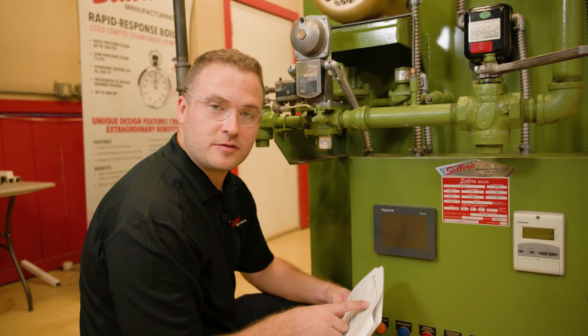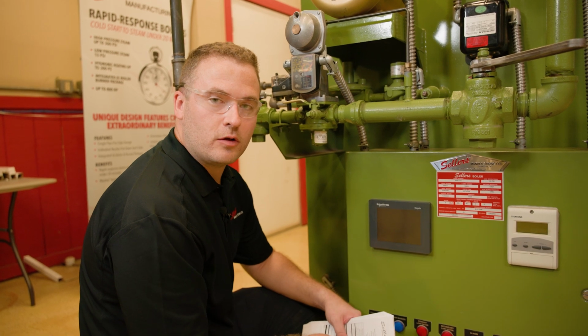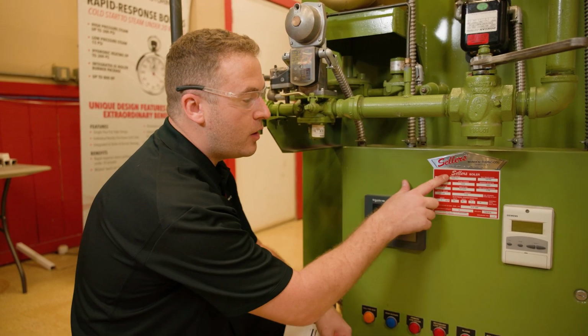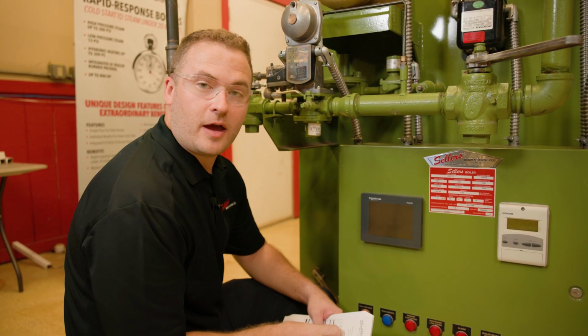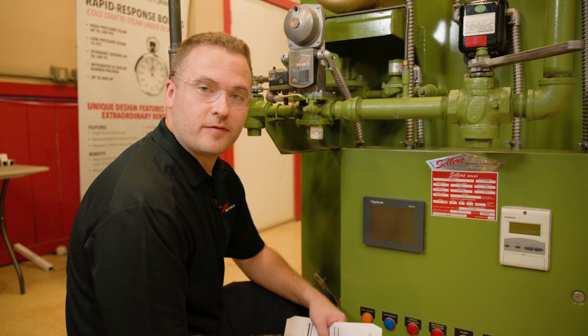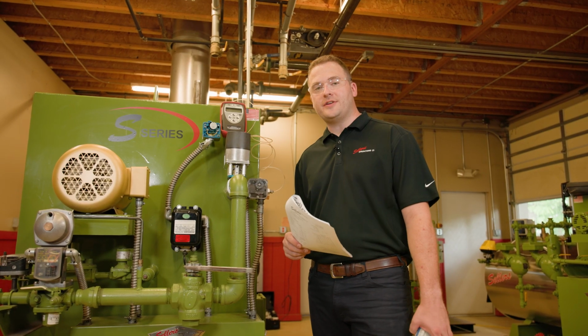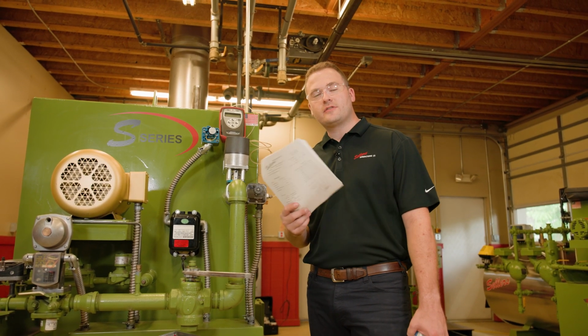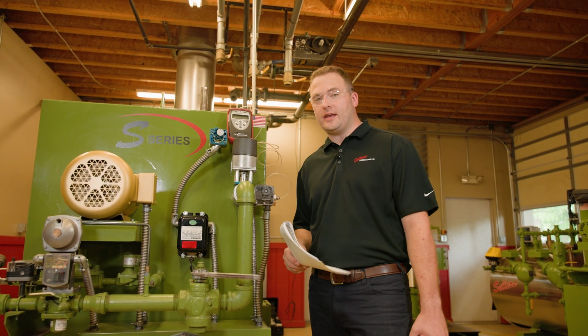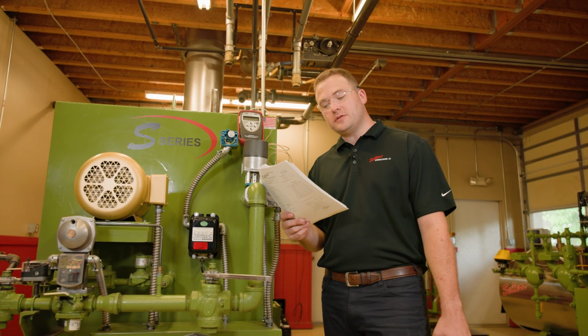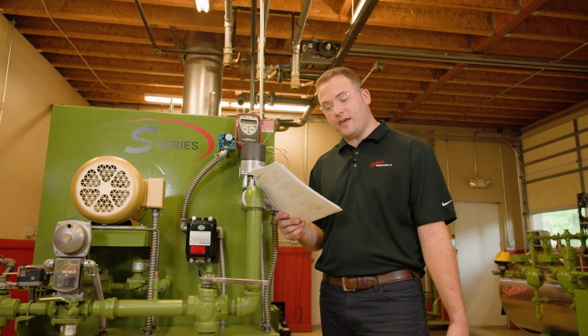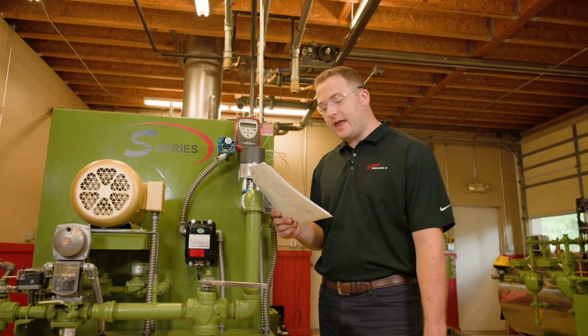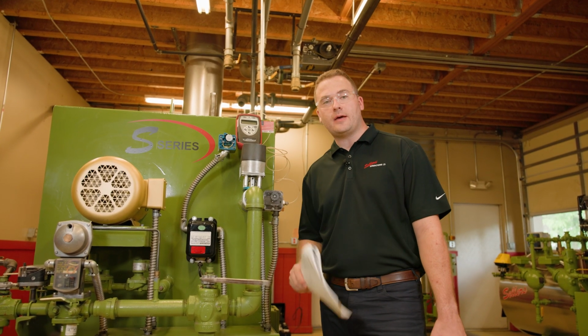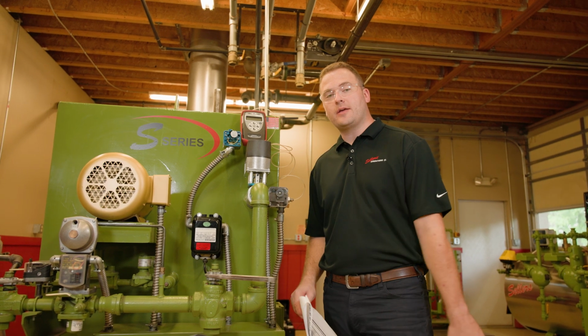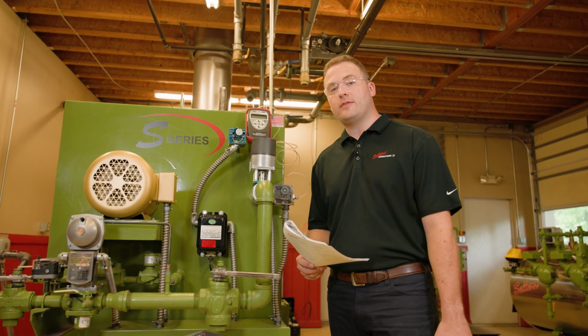If you do not have a test report, you can contact your local Sellers Manufacturing rep with the model number and the serial number, and they'll be able to get you the proper information. Now that we have the proper factory test record for this boiler, let's go over the information and where you can find it. So for the stack O2, stack CO2, stack CO, stack NOx, and then the stack temperature and ambient temperature, you can use your calibrated combustion analyzer in order to get those settings.